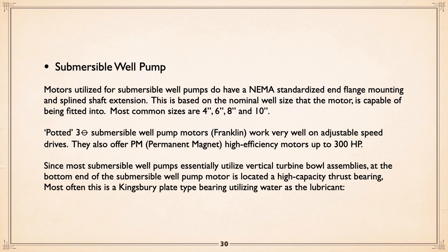Since most submersible wells essentially utilize vertical turbine bowl assemblies, at the bottom end of the submersible pump is a high capacity thrust bearing. In other words, the thrust of a vertical turbine is down and the motor is up high, so the thrust is pulling down on that motor. Here the motor is under the pump. The submersible motor is under the pump. So that's a compression force, again, forcing down. So the motor has to be able to tolerate that force down on it, which can be fairly high. So they have a high capacity thrust bearing at the bottom.